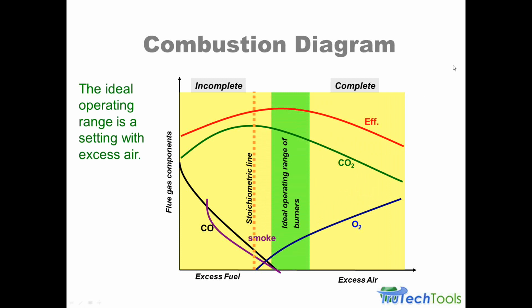And here's where most manufacturers in general would like to see you operating burners and boilers, in a range where there's a moderate amount of excess oxygen, but not too much, such that you kill the efficiency, but also such that you have almost no smoke present in an oil burner and very low levels of CO present, the black line. So this is the operating range on the excess air side.